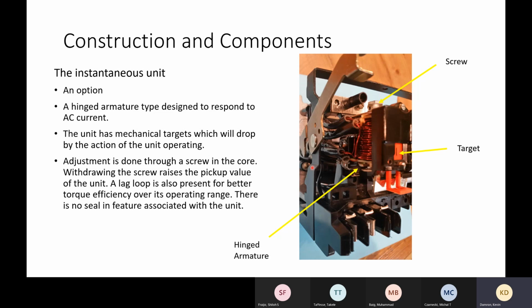If the relay has a 50 element, which that first picture didn't, then it's going to be a coil that looks like this. And where I was talking last week about there's a screw in the top, it's pretty simple. So really, this is just a coil that we pass current through, and it's a plunger type device. So a technician will adjust this screw until he gets the right amount of current to operate it that he wants. Again, it has a hinged armature, so it's a plunger type device. When it operates, it moves and closes a contact, and again, completes your trip circuit, and it drops a flag.